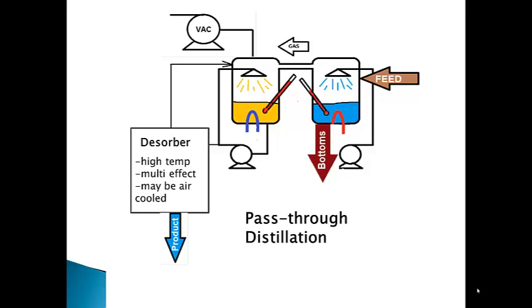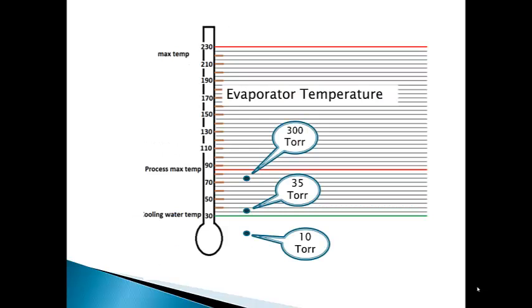The size of the vacuum pump must be matched to the rate of incoming non-condensable gases and to the system's operating pressure. Vacuum pumps, after all, are volumetric devices, and the volume of gases varies inversely with the absolute pressure. If you are operating at 50 torr and decide that you want to change to 25 torr, the size of the vacuum pump must be doubled. Let's keep this in mind as we move on to the topic of evaporator temperature.